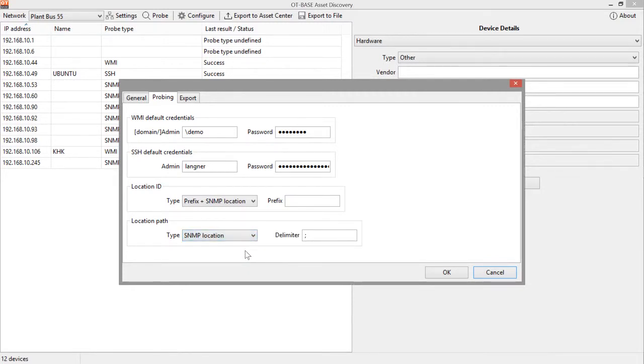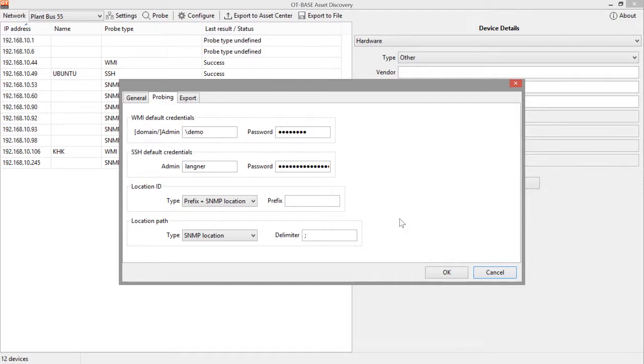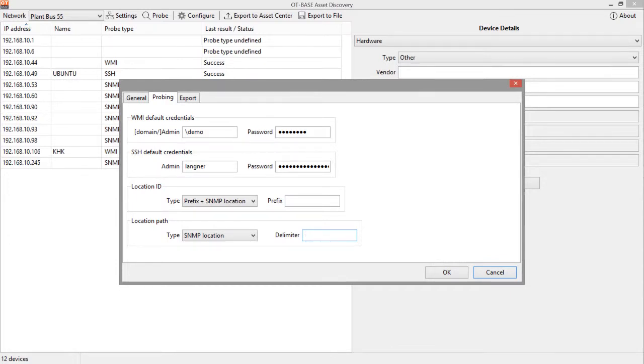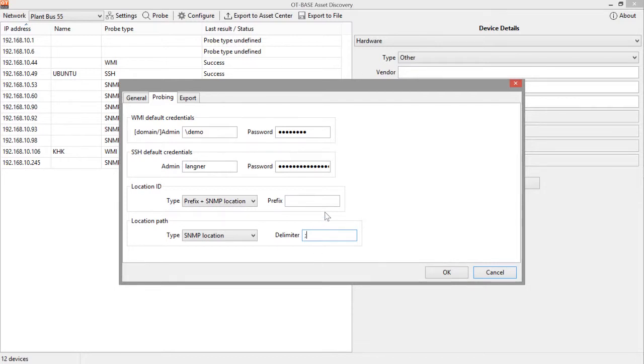Again, this could be coded in the SNMP location data field. And if that is the case, the difference to the location ID is that a location path always uses delimiters to distinguish between the various components of that path. And you have the opportunity in this field to specify which character is used as a delimiter. In many cases it is just the semicolon, but it could also be a slash or a dash or whatever the person who stored that data thought was appropriate. And by telling OT-BASE which character is used as a delimiter, OT-BASE can make sense out of your data and translate it to the more standardized form that is used in the OT-BASE asset center.